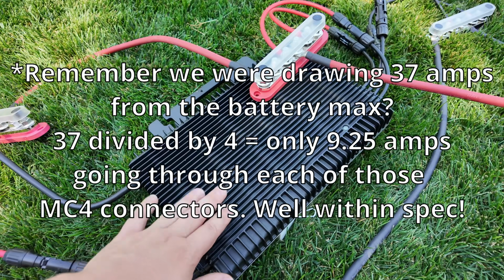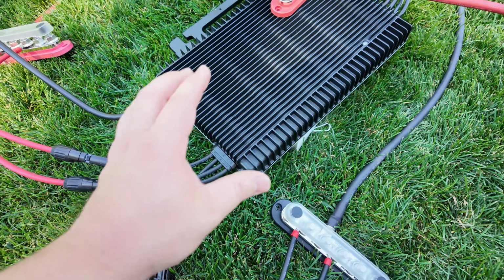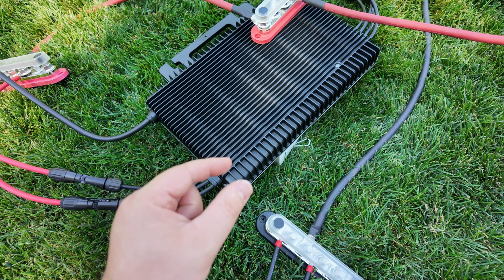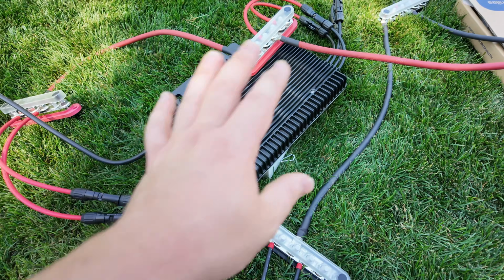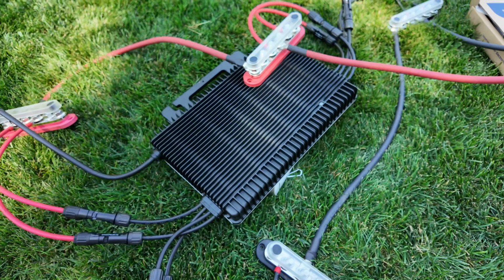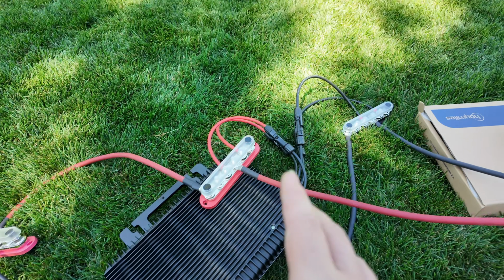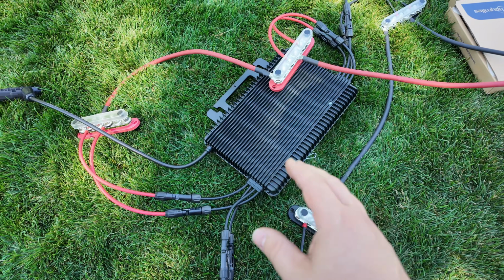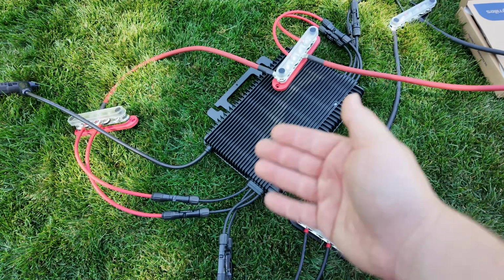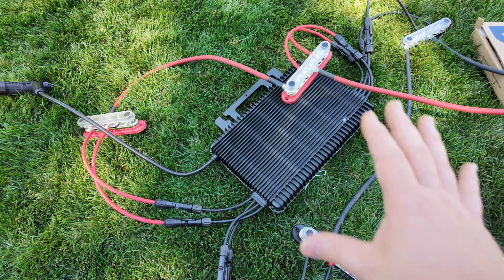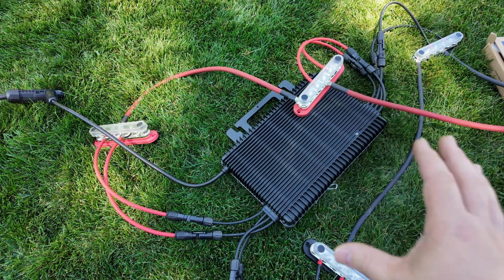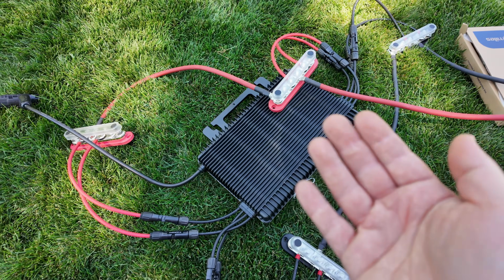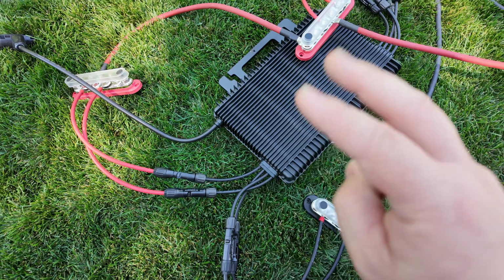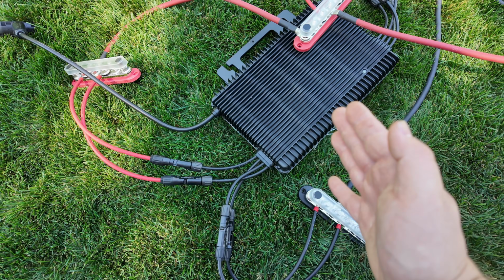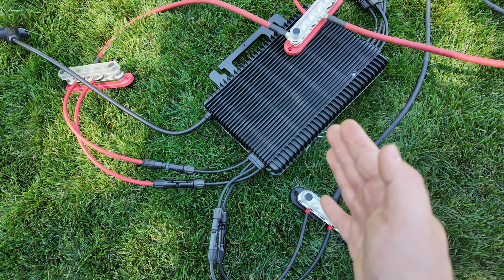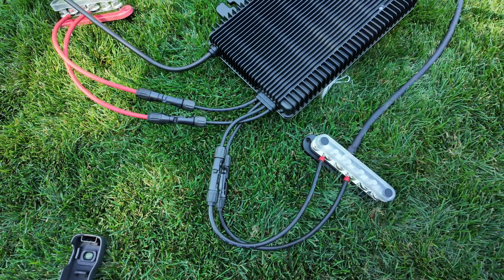Why? This inverter is special. Every single input has its own MPPT controller assigned to it, so there are actually 4 MPPT controllers inside this inverter before the inverter portion. As long as you do not exceed the voltage of those MPPTs, they will self-regulate how much current they pull. Voltage is pressure, amps is the flow or current. If we do not overpressurize the system, those MPPT valves, so to speak, will only let through the amount of current they're designed for at any given time, and they'll self-regulate that current. I hope that makes sense.